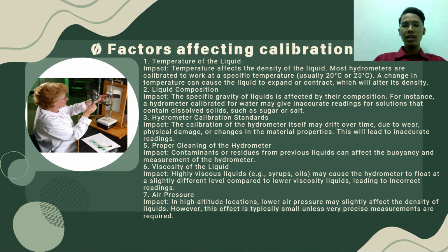Thirdly, hydrometer calibration standard. The calibration of the hydrometer itself may drift over time due to wear, physical damage, or changes in the material properties. This will lead to inaccurate readings. Proper cleaning of the hydrometer: contaminant residues from previous liquid can affect buoyancy and measurement of the hydrometer. Viscosity of the liquid: highly viscous liquids, for example syrup and oil, may cause the hydrometer to float at a slightly different level compared to lower viscosity liquids, leading to incorrect readings.